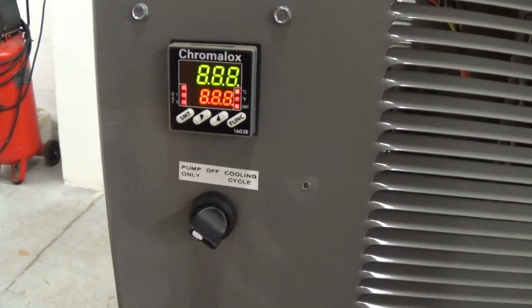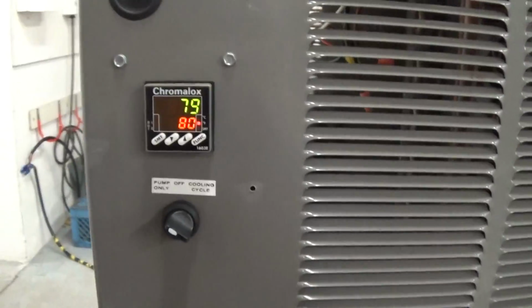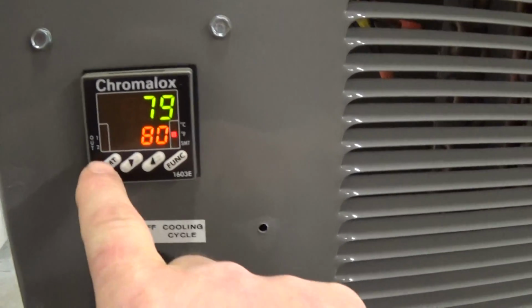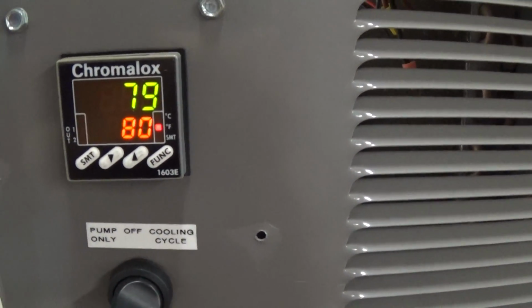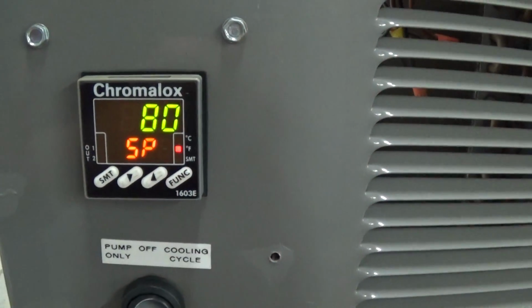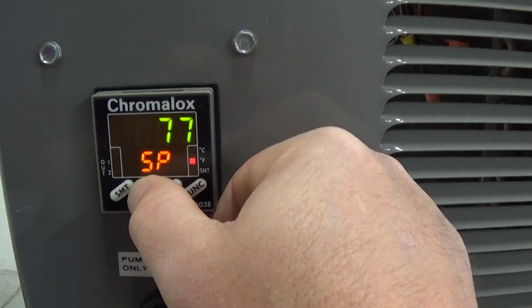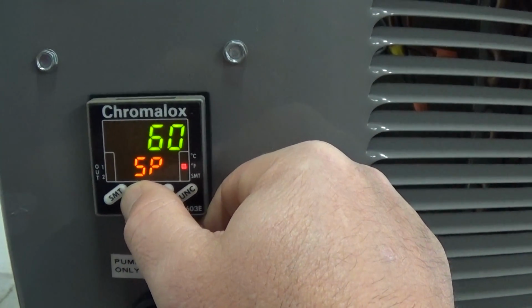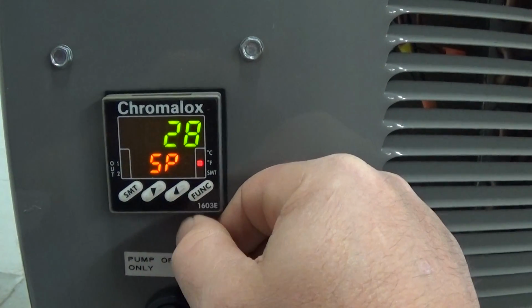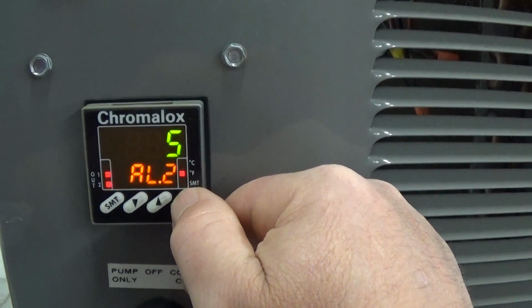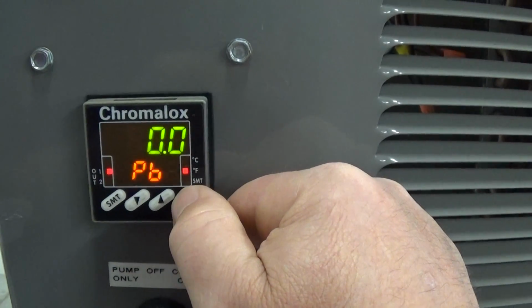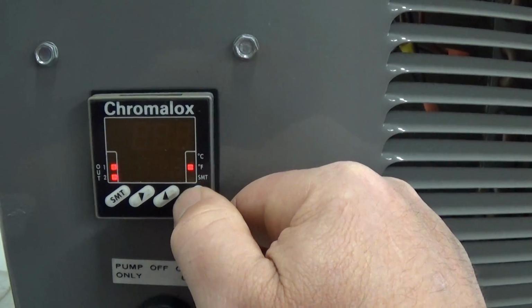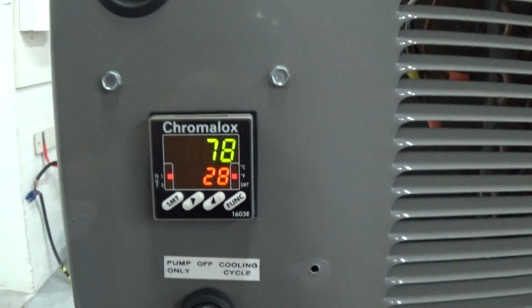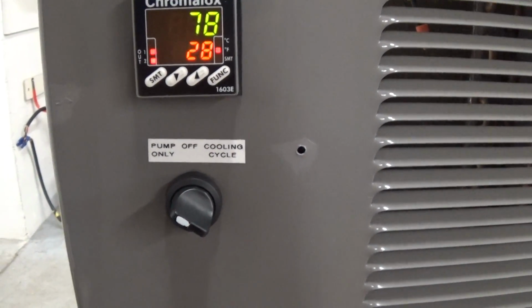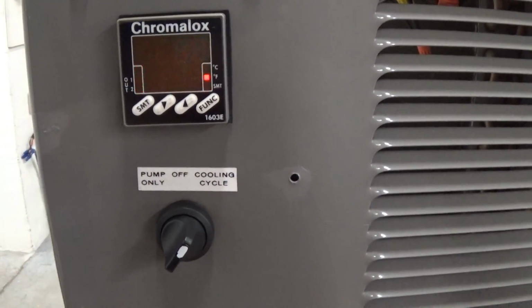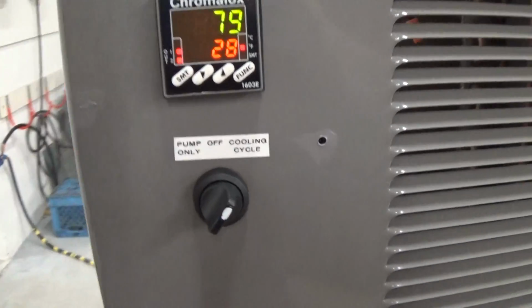So we're going to turn it on pump only. With the controller, you don't have to worry about the SMT, which is the Smart Test button. All you need to do is go to Function. That brings you to the primary set point. And for this test, we're going to lower it to 28 Fahrenheit. The other ones are alarm codes and stuff, and we can walk you through those if needed down the road, but you shouldn't have to worry about that. So then when you change it to cooling cycle, that's when it should start chilling, as you hear.